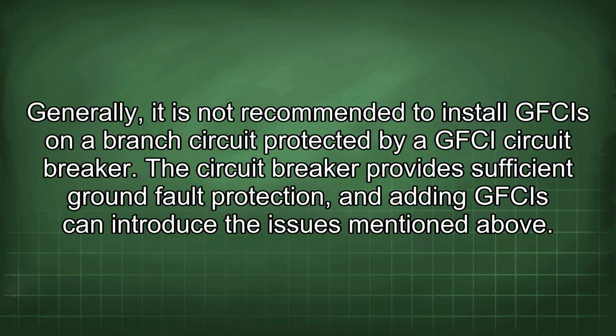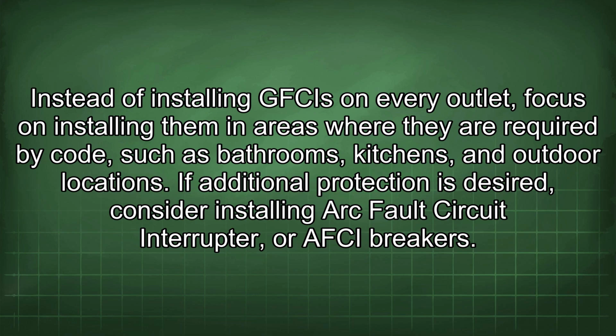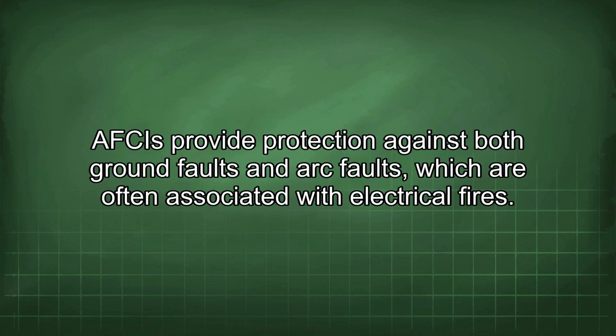Generally, it is not recommended to install GFCIs on a branch circuit protected by a GFCI circuit breaker. The circuit breaker provides sufficient ground fault protection, and adding GFCIs can introduce the issues mentioned above. Instead of installing GFCIs on every outlet, focus on installing them in areas where they are required by code, such as bathrooms, kitchens, and outdoor locations. If additional protection is desired, consider installing arc fault circuit interrupter or dual function breakers. Dual function breakers provide protection against both ground faults and arc faults, which are often associated with electrical fires.